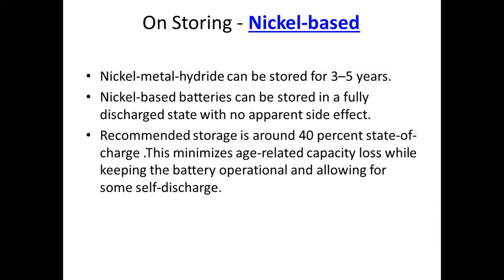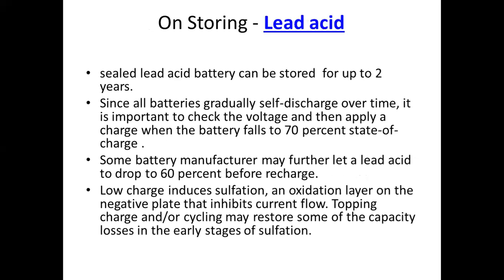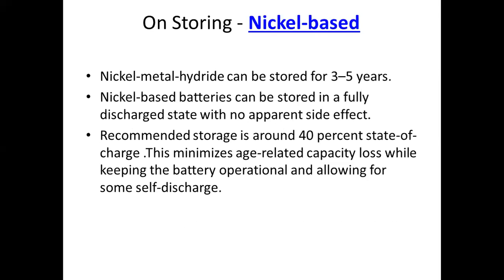For example, in lead acid, if I'm storing the battery at 12 volts, due to the specific gravity, the voltage measured after a particular time will be around 12.42. So there is a contribution of specific gravity to the battery, giving you a change from 12 volts to 12.42 volts for lead acid. This is one of the standards for making lead acid batteries: the specific gravity is this much, the battery should be this, and the difference at 70 percentage should be like this.